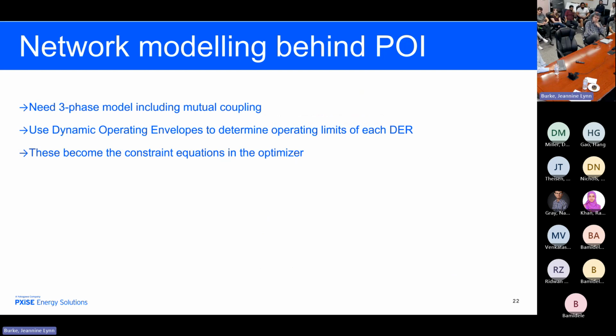Okay. Now, just a few minutes on network modeling. All of you are familiar with network modeling. I believe that a 3-phase network flow program is required. It should run inside the microgrid. It doesn't have to be a big one. It can run very fast, at 1-second intervals, and solve the load flows from within the microgrid controller, so that when the next dispatch is made, you can check the model to see, will this P cause a thermal or voltage constraint anywhere on my network?